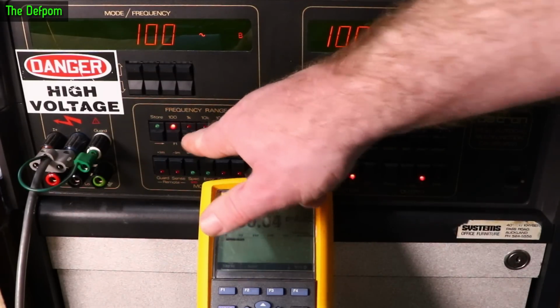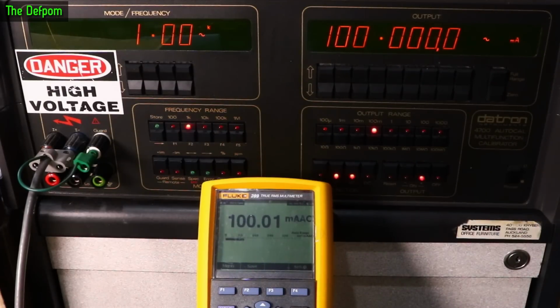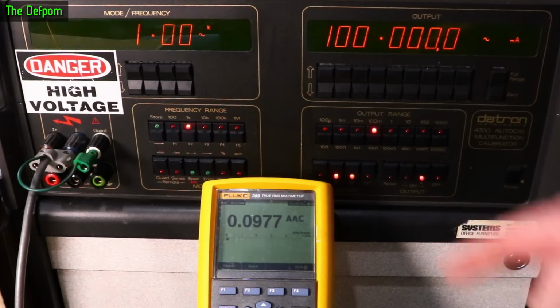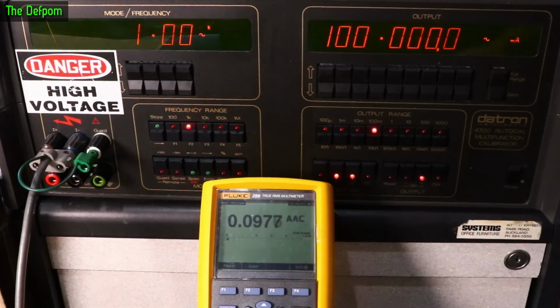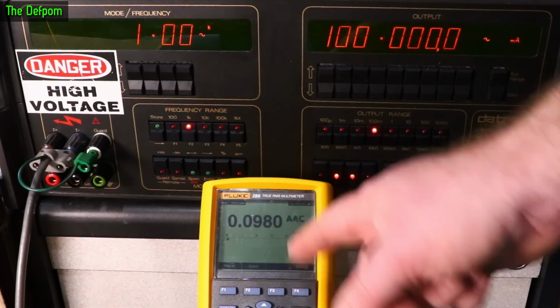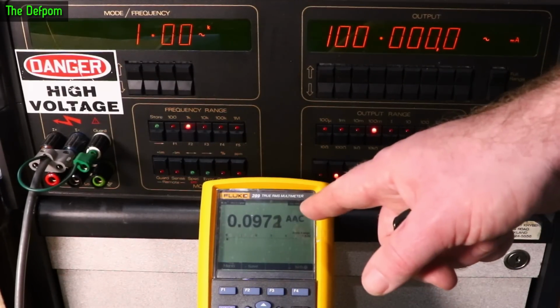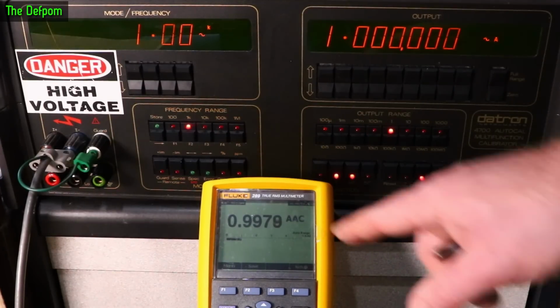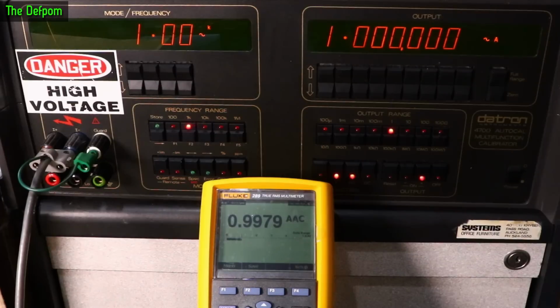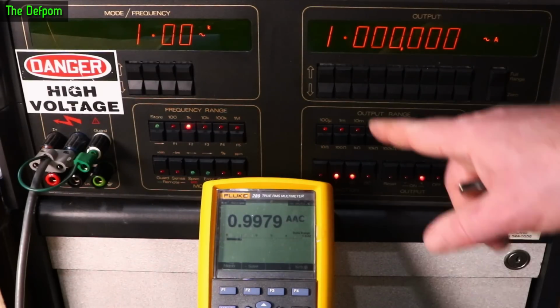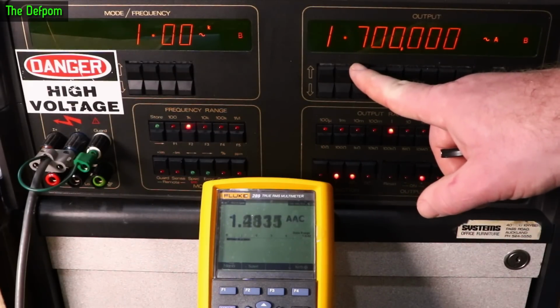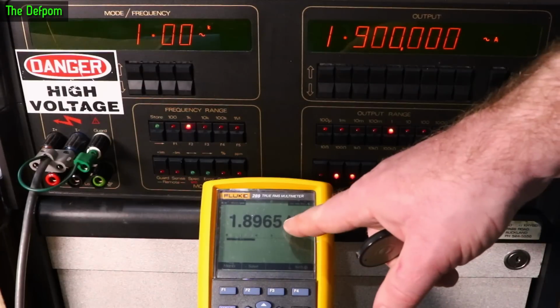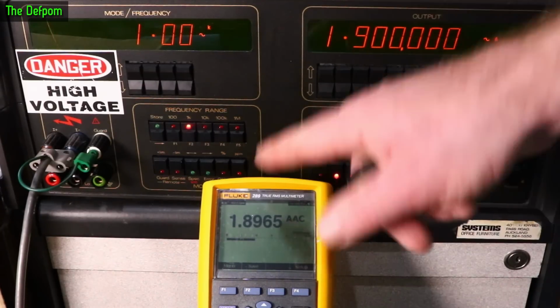Let's change frequency to 1 kilohertz, and that's actually looking pretty good there. Let's change to amps. So 100 milliamps, 1 kilohertz is reading a few counts down, well 20 odd counts down I suppose you could say. 2 or 3 milliamps down. So 1 amp is also about the same kind of effective scaling, about 3 milliamps down, 2 to 3 milliamps. Let's go to max, and you can see we're about 3 milliamps down still at 1 kilohertz.